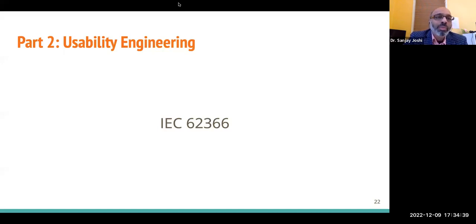Now, there are situations when the design change you are making to your product triggers a new submission, because you're changing the intended use or some operating principle. You have to go back to the government and say that now my users are going to use this device in a different way. That usually means you could call it an extension of the device, and you typically need a new design history file for that. What you want to tell the government is, until you approve this change, this extension, I'm not going to ship it with my device. So you don't want to modify the design history file of your original device.